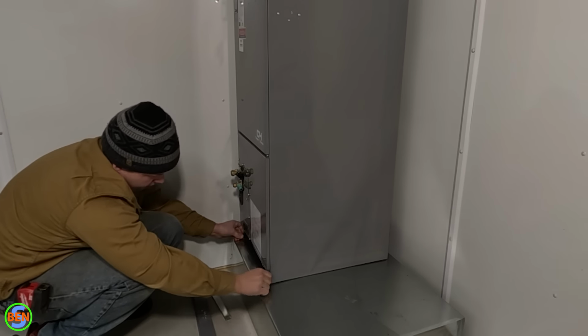Also note that codes vary in different areas with the ductwork and the way that you install it, so always check with the authority having jurisdiction. Some jurisdictions or areas require that there be a disconnect located inside of the room for that unit. Obviously, since we're powering this thing from the outside unit, we are actually not able to just turn the power off right inside of this mechanical room here, and so sometimes adding an additional switch or a means of disconnect on those conductors coming to the unit may be necessary.